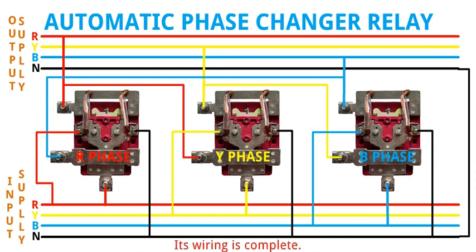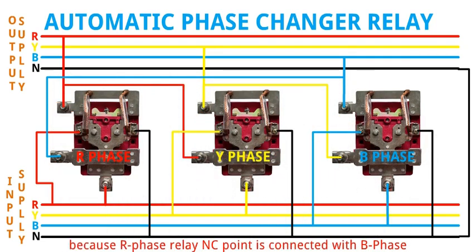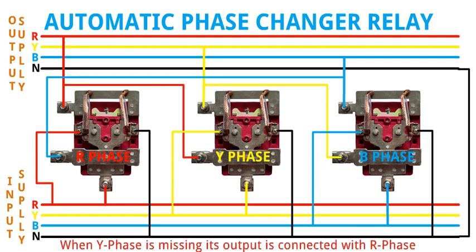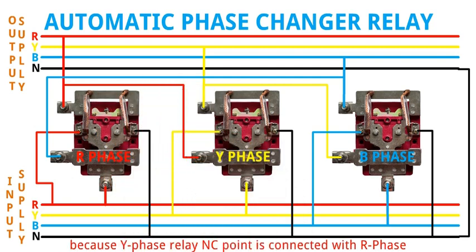And it works like this: During failure in R phase, its output is connected with B phase, because the R phase relay NC point is connected with B phase. When Y phase is missing, its output is connected with R phase, because the Y phase relay NC point is connected with R phase.